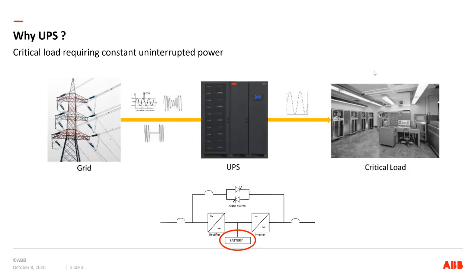The basic function of the UPS, and this single line is the double conversion online UPS, which is 99 point something percent of UPSs in the market, is that the input AC power from the utility or the generator comes to a rectifier. The rectifier rectifies that AC power to DC and feeds it onto the inverter, and the inverter then chops it up and creates clean power for the critical load. What makes this whole device uninterruptible is that there are two power sources on the DC bus between the rectifier and the inverter. The rectifier is the normal mode, and if power fails from the utility, or while switching to a generator or back again, the inverter will just take power from the battery. It doesn't care where the DC power is coming from. As long as there's DC power, it will continue to feed clean power to the load. That's the basic function of the UPS.